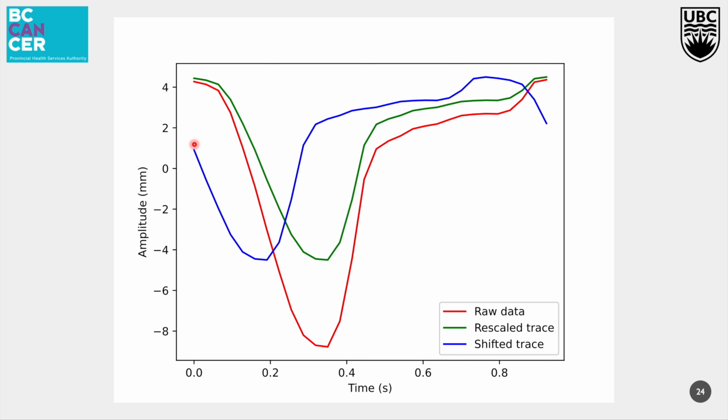The reason for this shift is just because with the way the cardiac phantom works, it will mess up a little bit if the start isn't fairly close to 0, so that shift was just done to make sure that doesn't happen. Then for the study, we had 3 amplitudes we chose, 3, 6, and 9 millimeters, and a heart rate of 65 beats per minute were used throughout.